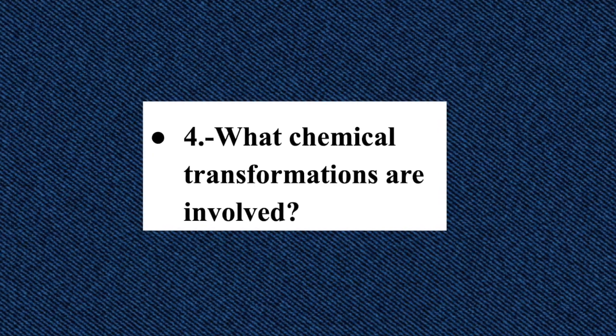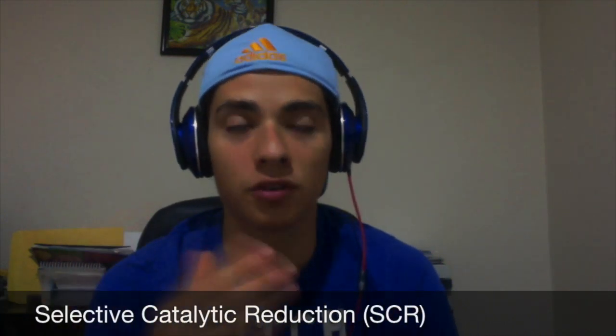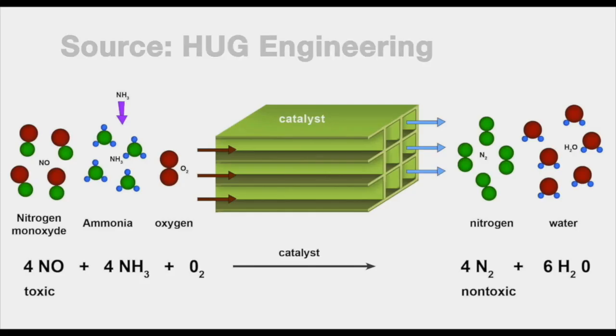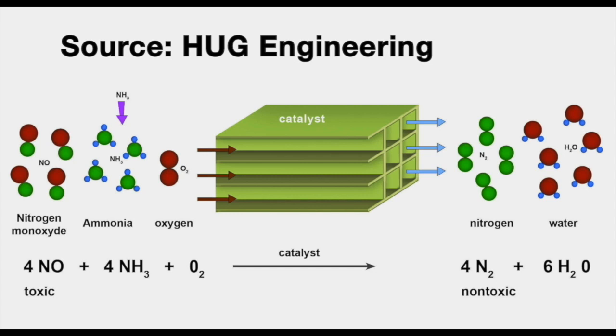Question four: what chemical transformations are involved? The purpose of this chemical process is the transformation of nitrogen oxides into inert gases. Two species must be present: a reductant must be added to the flue gas which contains the nitrogen oxides, and with the selective catalyst, a redox reaction takes place. The reactant species are the nitrogen oxides and the reductant gas — in our assessment, ammonia — which are transformed into nitrogen and water vapor, which are no longer harmful for the environment.